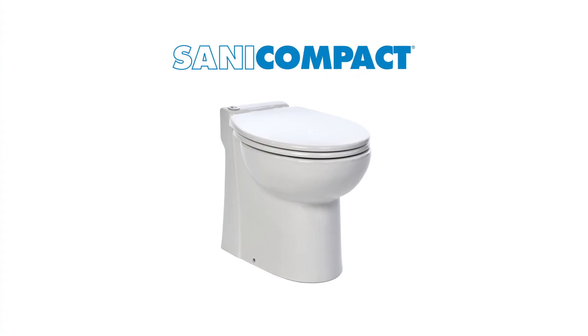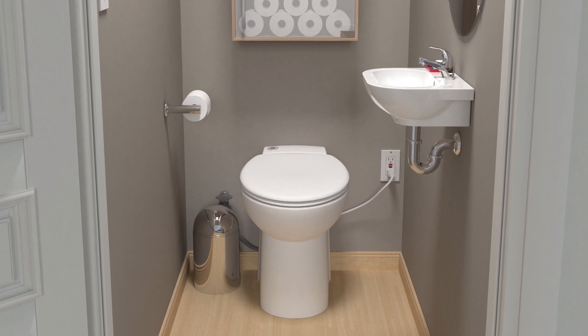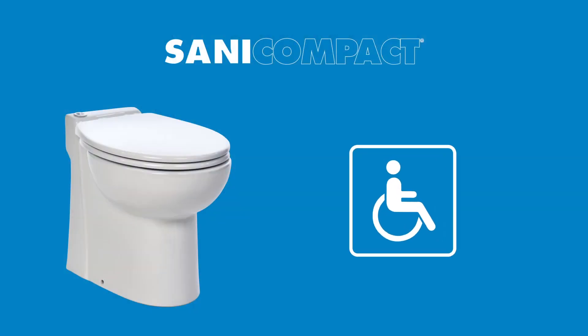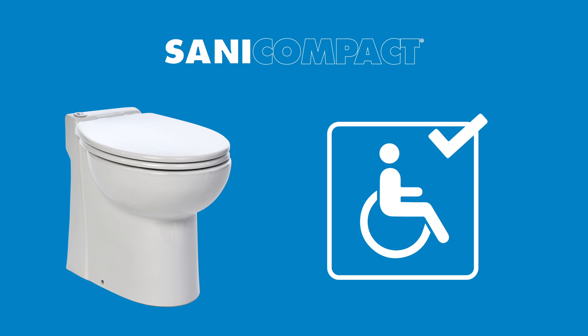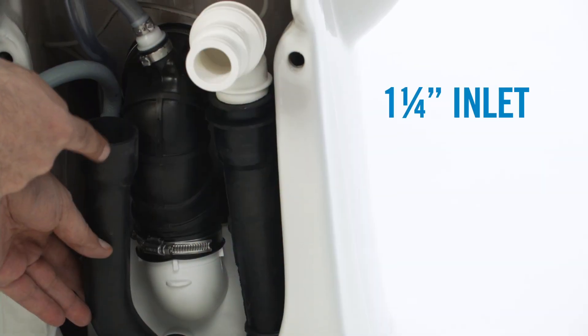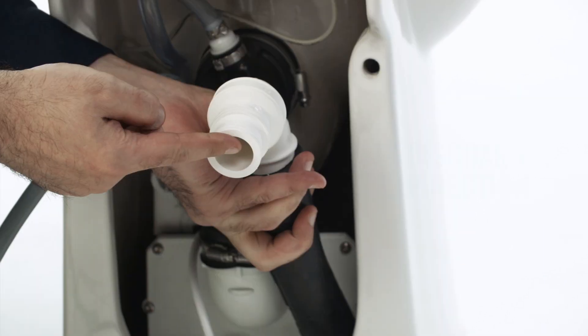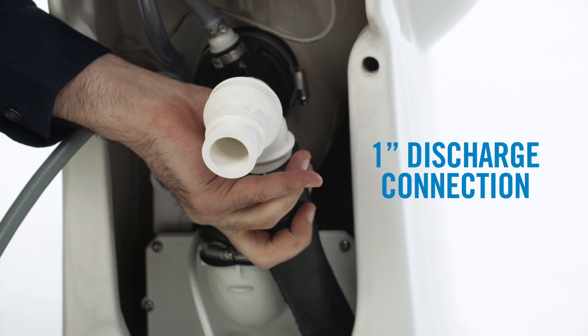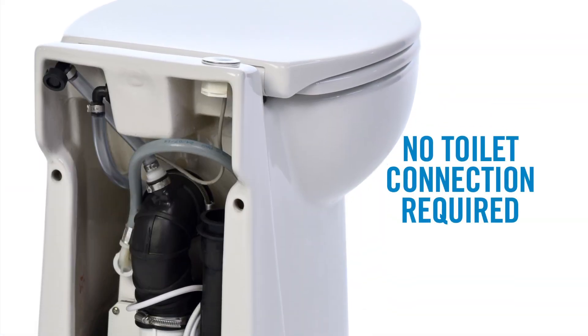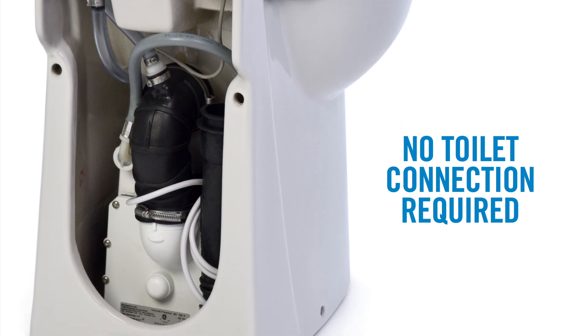Let's first take a look at the Sani Compact model. It's ideal for tight spots where a conventional toilet can't fit. The Sani Compact is also a great option for people with physical limitations requiring easy access to a toilet. The unit has a one-and-a-quarter-inch inlet on the back side for connection to a sink and a one-inch discharge connection. Notice that the pump is built into the toilet, so there is no need to have a toilet connection like our other Saniflo systems.